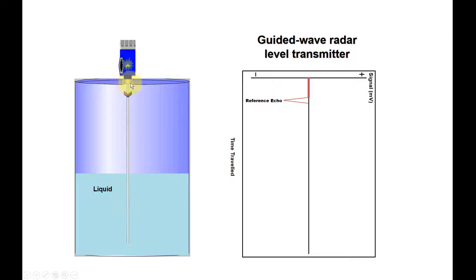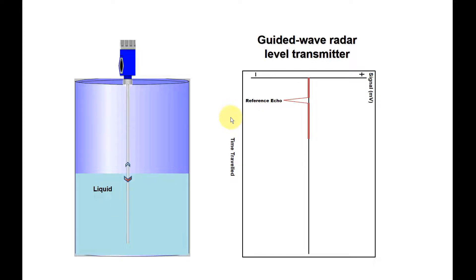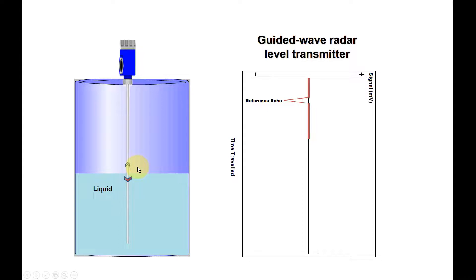Near the flange of the level transmitter, the radar signal will continue to travel across the level probe, and you can see the signal or the waveform moving this way. It continues to move until it reaches the liquid surface. Then you can see the echo or the radar signal bounce back, because here there is a liquid surface — the signal bounces back due to the difference in density or dielectric constant.